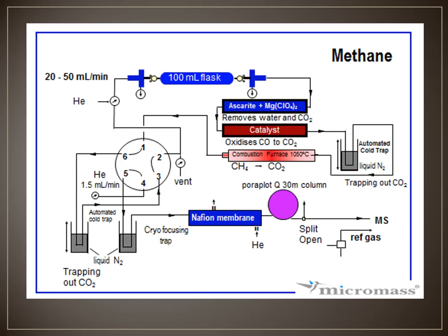Then later the extra gas that will contain only methane will use oxidation under high temperature, here cited as 1050 degrees, to transfer the methane into carbon dioxide.